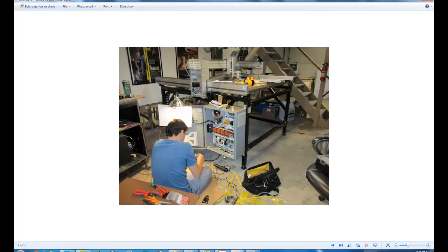It's made by Roxtec, where you take these split cables and don't have to cut any cables, even a parallel cable. They just come through and you put these little split glands in. I think they're much better for this application, not having to cut some of them, especially the parallel cable, and do a termination for that coming into the panel.